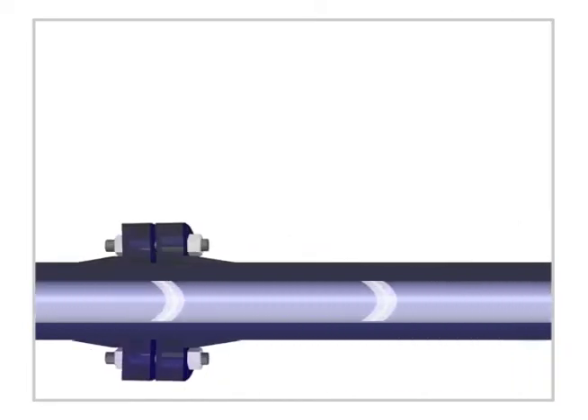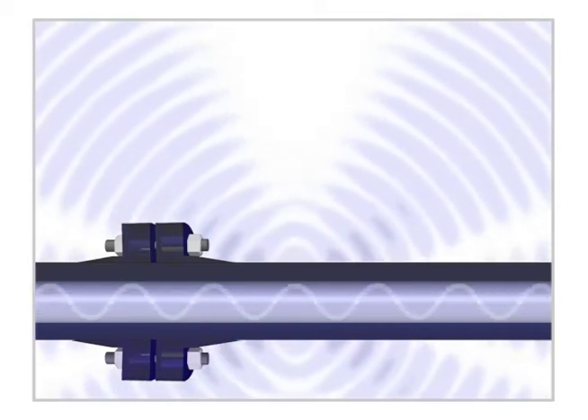As the turbulent flow field passes through a sufficient length of pipe and encounters no further disturbances, the turbulence is reduced and decays to normal turbulent pipe flow. However, the acoustic field generated by the turbulent pipe flow persists and creates externally radiated noise.